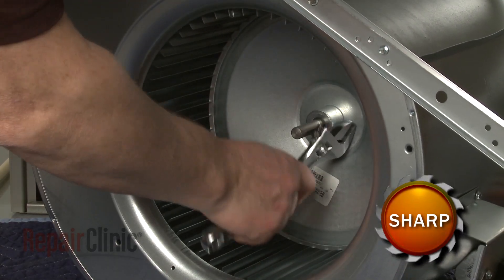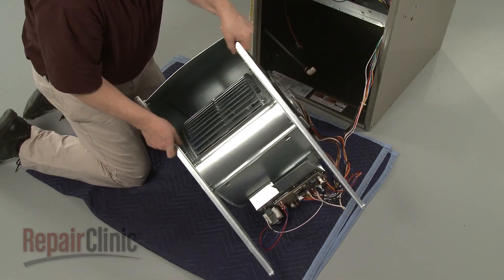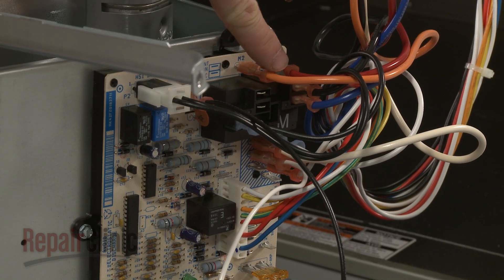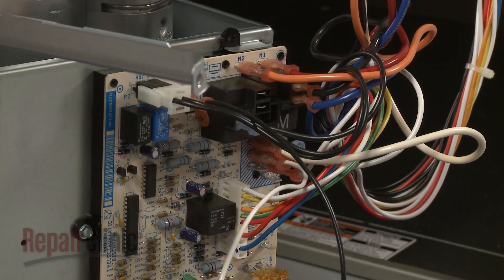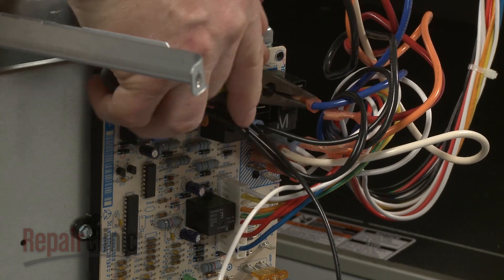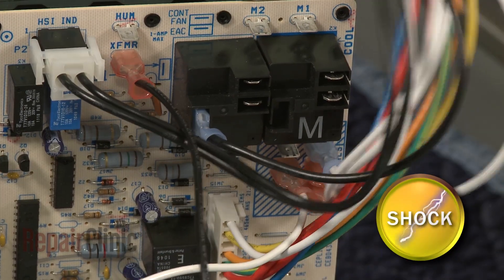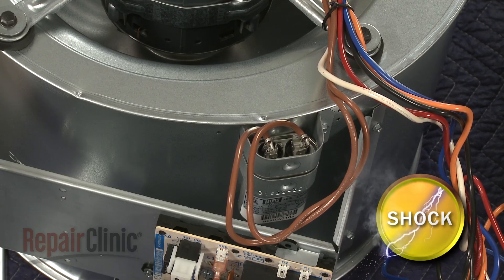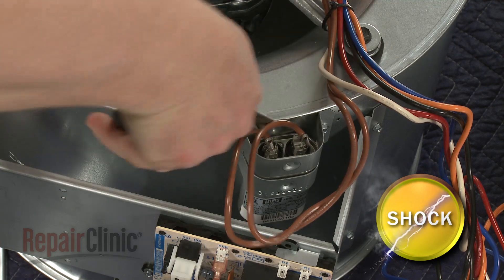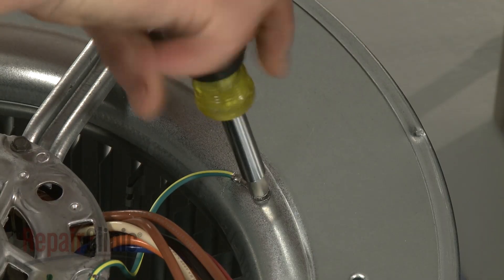To remove the blower motor, use a nut driver to loosen the blower wheel set screw. Now set the blower assembly on its side. Note the orientation of the motor wires connected to the control board, then disconnect them. To ensure the capacitor is discharged, place a screwdriver with an insulated handle across the terminals. Now disconnect the capacitor wires and remove the screw to release the grounding wire.